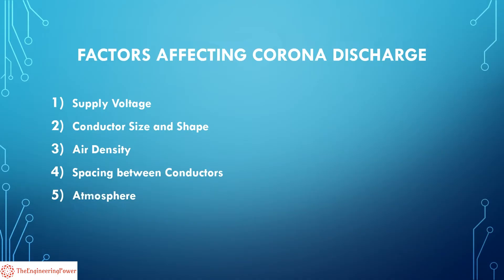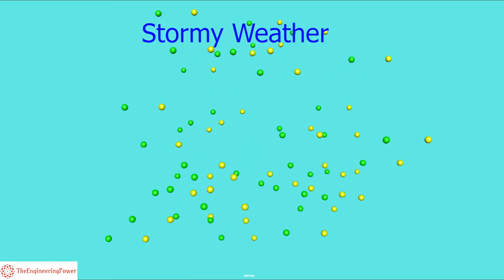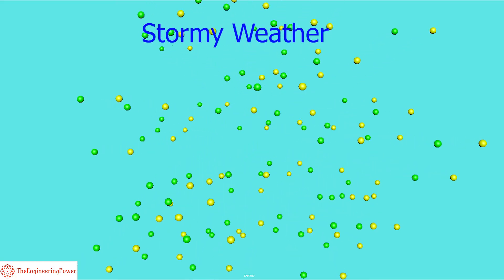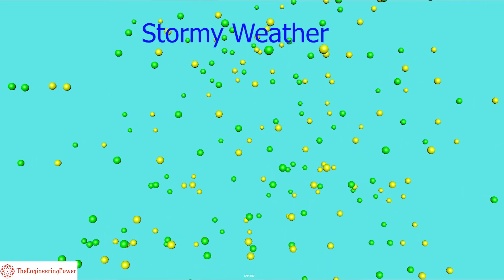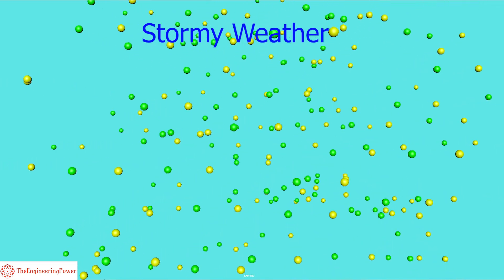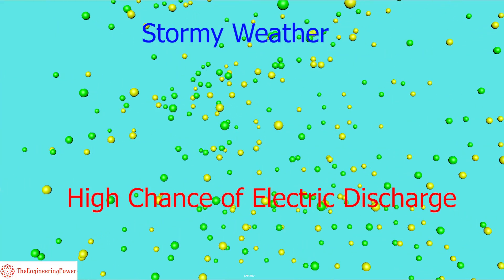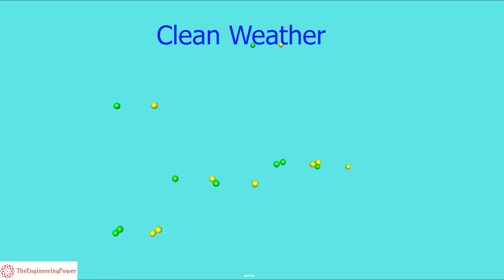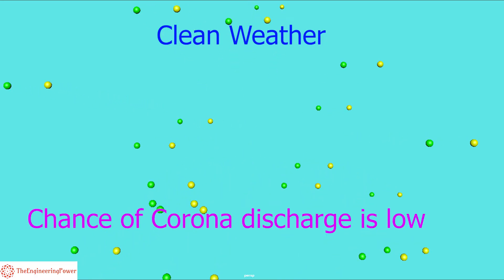Another important factor is the surrounding atmosphere. Since corona discharge occurs due to the ionization of air surrounding the conductors, it is highly affected by atmospheric conditions. In stormy weather, the number of ions surrounding the conductor is very high and there is a high chance of electric discharge, whereas in clean weather with normal airflow, the chance of corona discharge will be low.